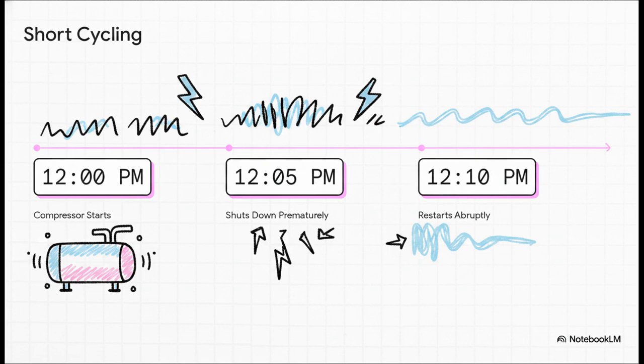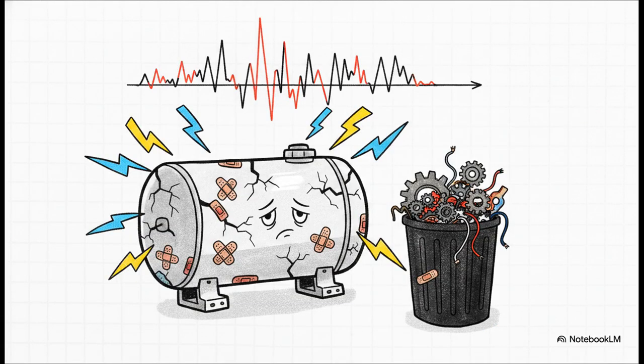Basically, the compressor violently starts up, runs briefly to drop the temperature, shuts down prematurely, and then restarts all over again just a few minutes later when the room warms up slightly. But a healthy, properly sized system should operate in nice, long, continuous cooling cycles to actually properly dehumidify the space. The cost of short cycling is huge.